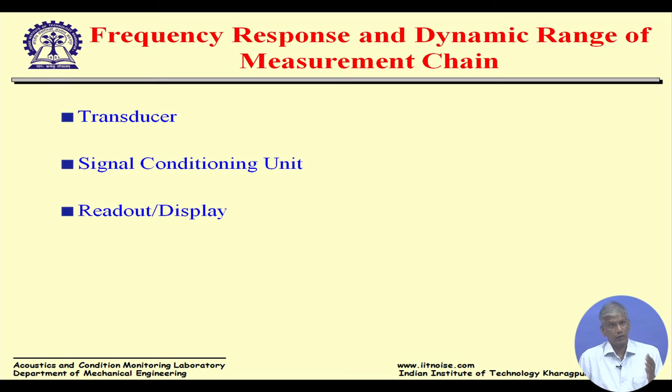So when you select transducers or combine transducers, you need to look into the manuals and find out what the frequency response is. And you can mix and match from your storage almirah, but then we have to be careful about these issues.